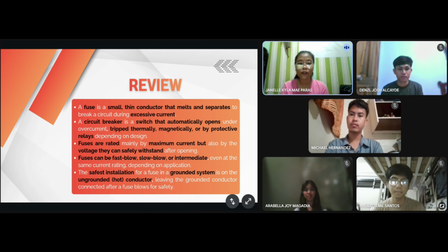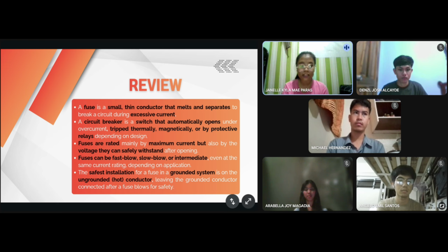So for our review, a fuse is a small thin conductor that melts and separates to break a circuit during excessive current. Next, a circuit breaker is a switch that automatically opens under overcurrent, tripped thermally, magnetically, or by protective relays depending on design. Fuses are rated mainly by maximum current but also by the voltage they can safely withstand after opening. Fuses can be fast blow, slow blow, or intermediate, even at the same current rating, depending on application.